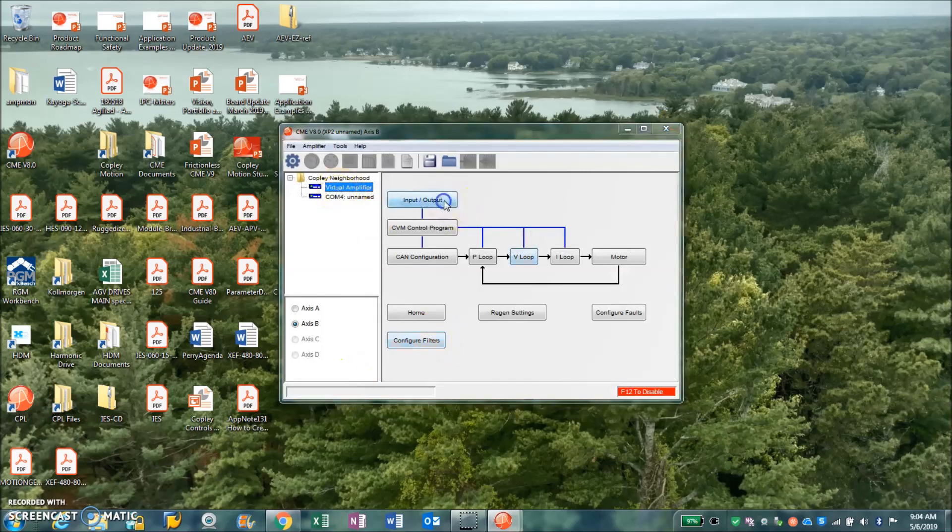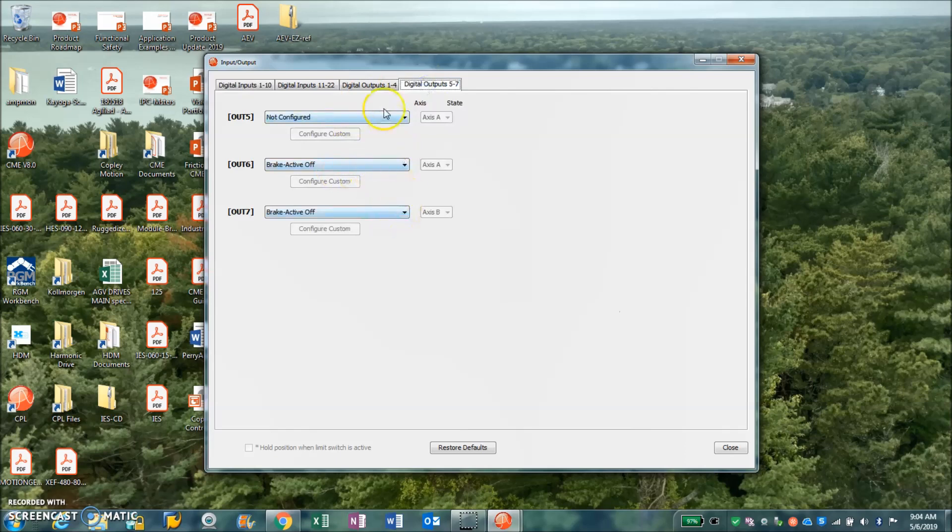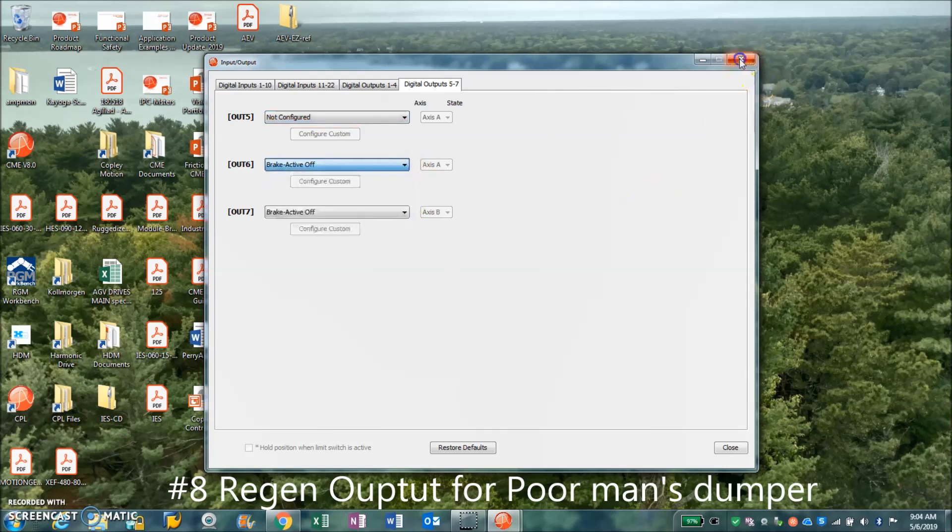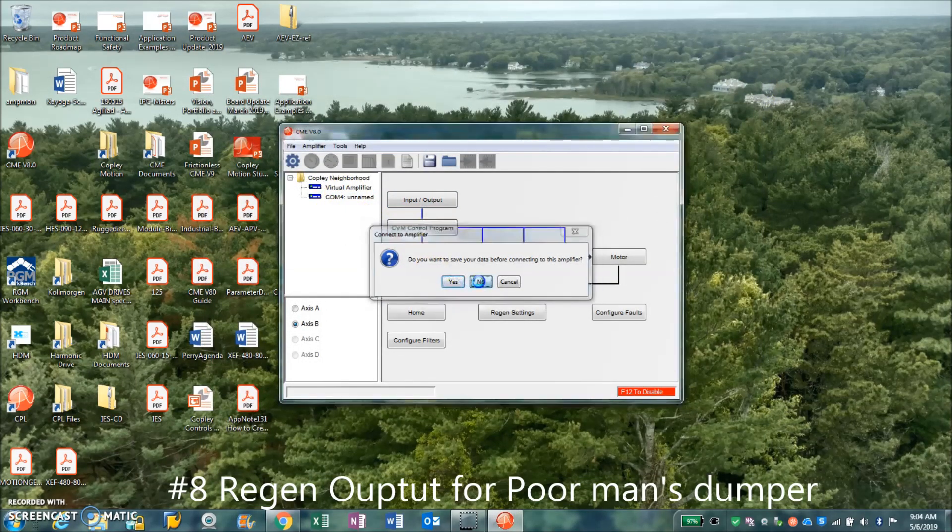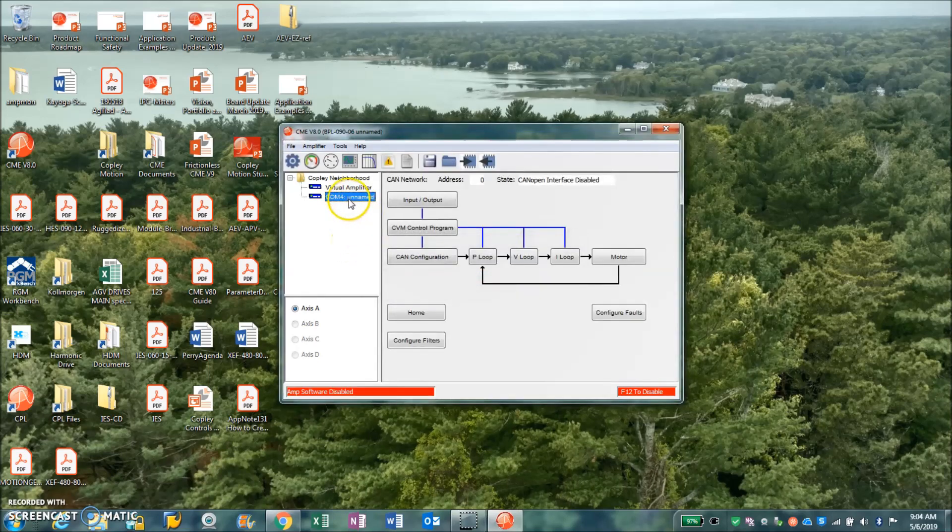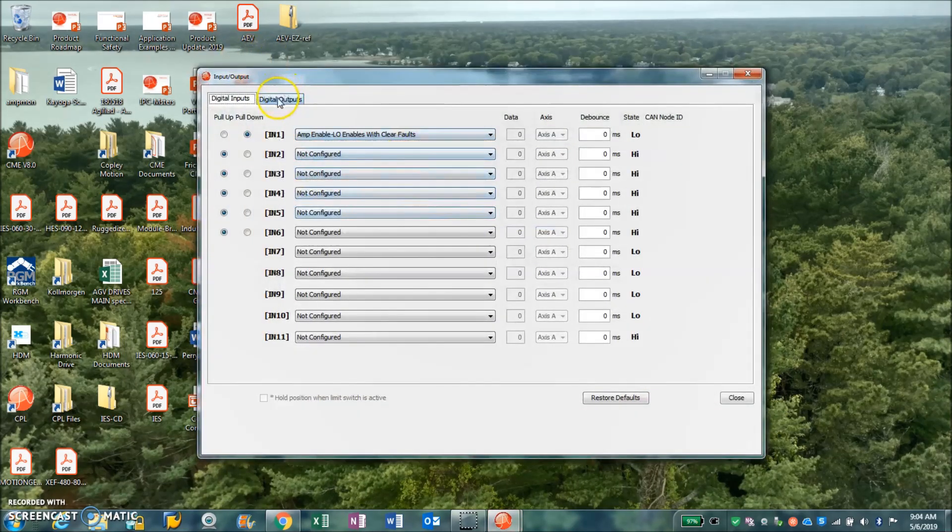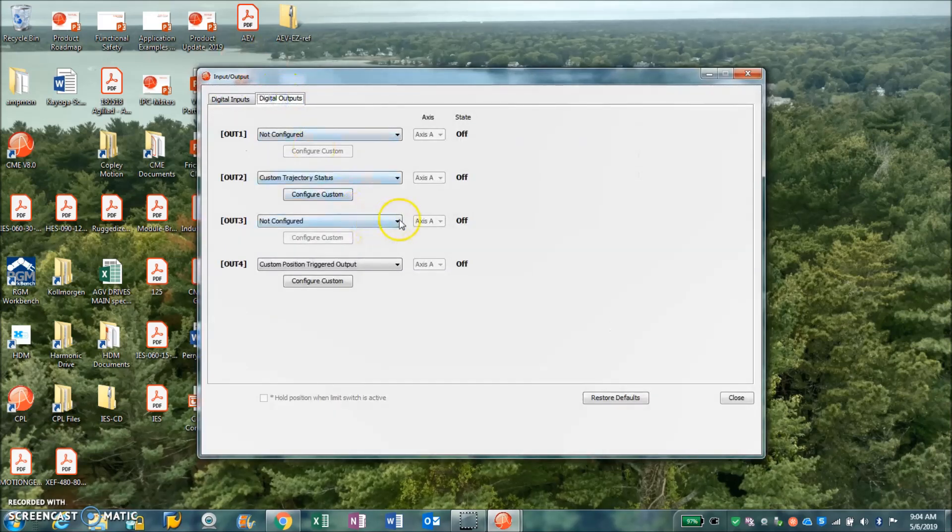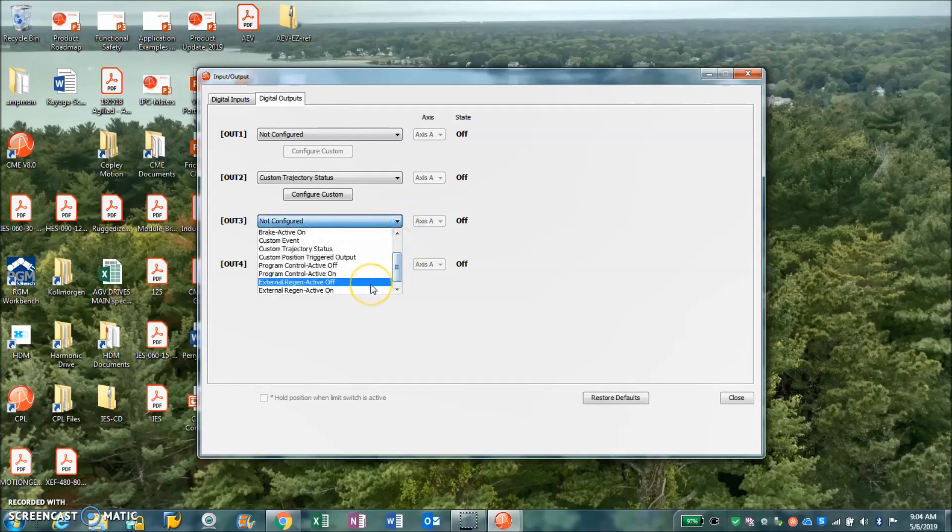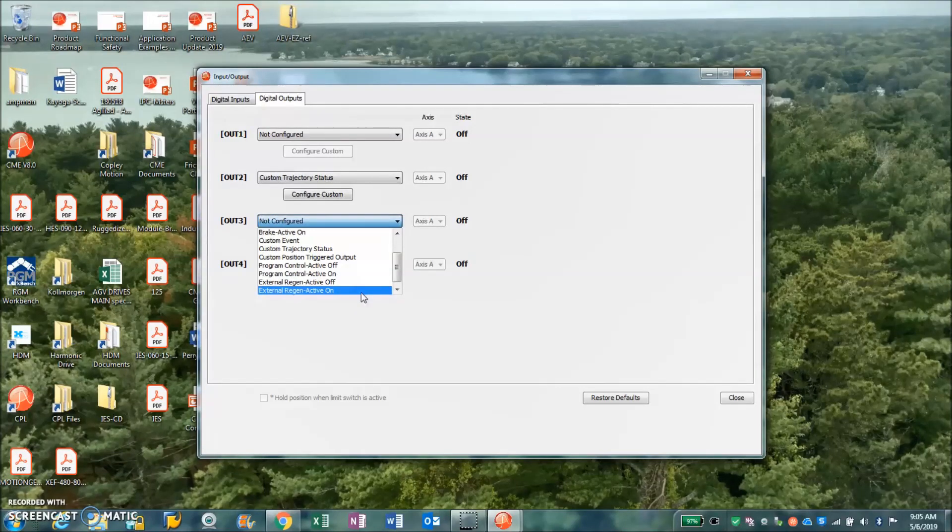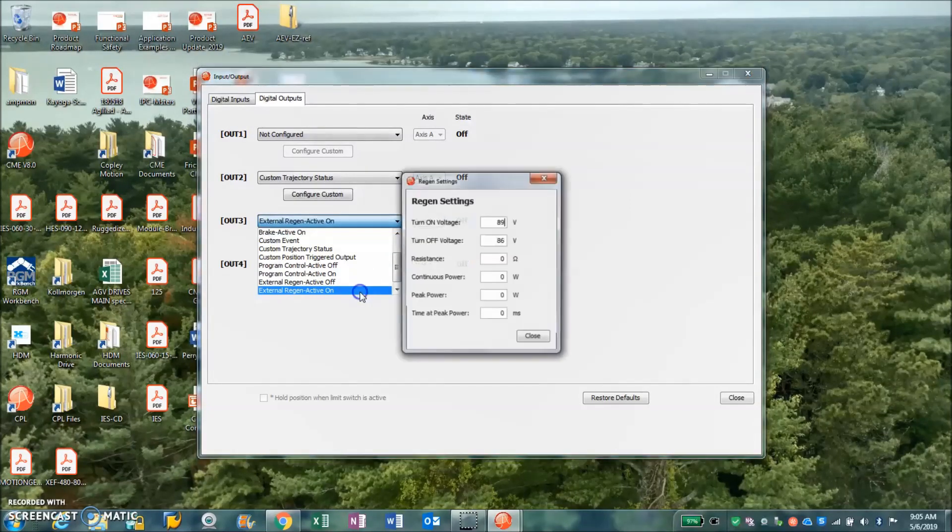Another feature that we'd like to talk about is on the outputs. Some of the outputs are configurable for regen. Let's suppose I have a high current drive and I'm pushing a lot of watts into the motor, and then it comes back at me. Do I need to buy a regen device? No, I'll just turn on an output to maybe a solid state relay and a resistor of my own design. External regen active on. So this turns on an output when the voltage exceeds some value. You can program like turn on at 89, that's before the over voltage shutdown, turn off again at 86.